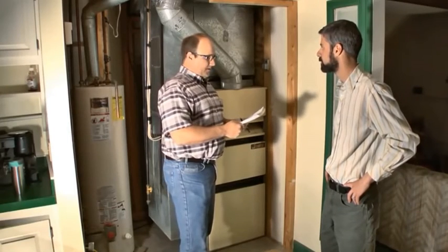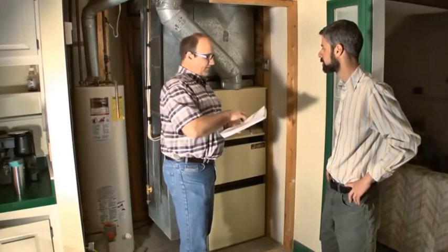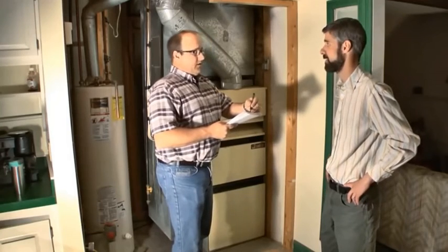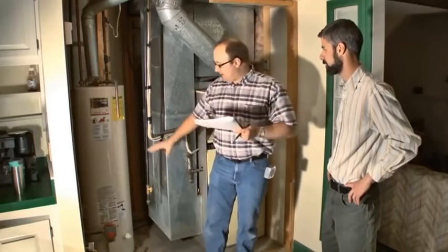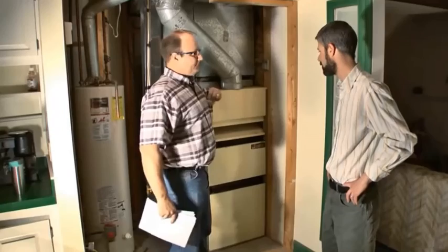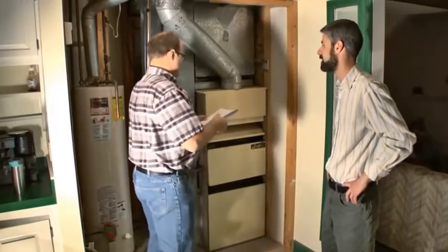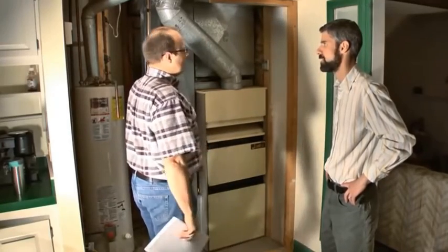And when I use the codes, it tells me that I need 50 cubic feet for every 1,000 BTUs. So I do the math, and it looks like... Is this going to make it? No, this is only good for 66,000 BTUs. So we're going to have to prescribe direct combustion air from outside into this room. Gotcha. And that'll make these burn better. All right. So what's our first step then, besides determining if it has enough combustion air?